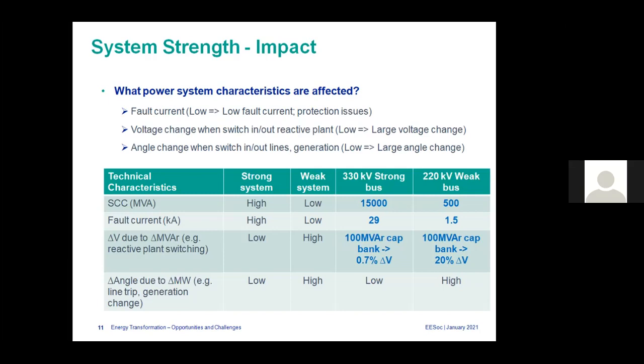As a rule of thumb, if you have a certain fault level, say 100 MVA, and a 20 MVA capacitor, then 20 over 100 will be the voltage change when you switch in that capacitor. So you can expect a 20% voltage change. But we know a 20% voltage change when you switch in a capacitor is not accepted. Normally, you would not expect anything more than 3% in Australia when you switch in reactive plant. So that's another issue with fault level.